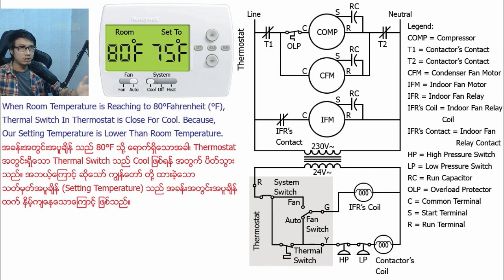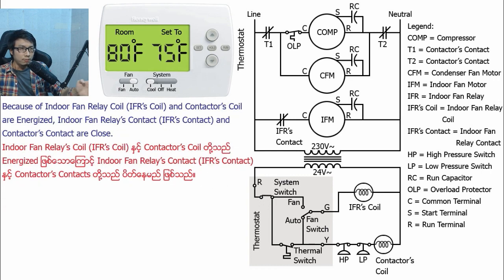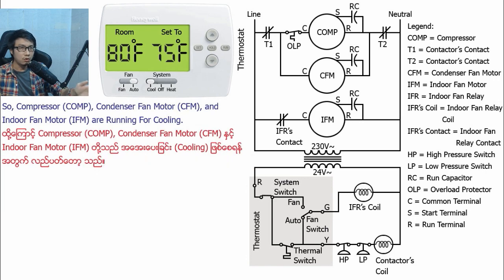When room temperature reaches 80 degrees Fahrenheit, the thermal switch in the thermostat closes for cool because the set temperature is lower than room temperature. At that time, the indoor fan relay coil and contactor coil are energized because 24V AC current is flowing into them. The indoor fan relay contact and contactor contacts are closed, so line and neutral current flows into the compressor, condenser fan motor, and indoor fan motor, and they are all running for cooling.